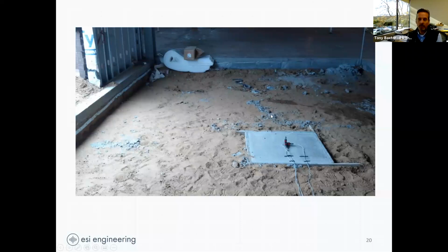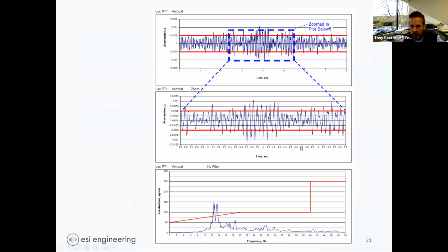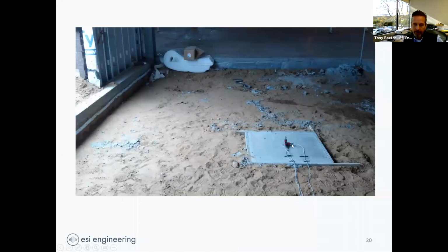So we made vibration measurements. Attaching accelerometers to dirt would seem more difficult, but our vibration levels are low enough that this sensor is probably just sitting there with some wax on the bottom attaching it to the concrete — we don't need to mechanically fasten it with a bolt or bond it tightly, because it's not moving much; the vibration levels are too low. Even out in the dirt, we'd just want a nice level surface, maybe packed down a bit so things don't move around, but the amplitudes would be the same in both locations.